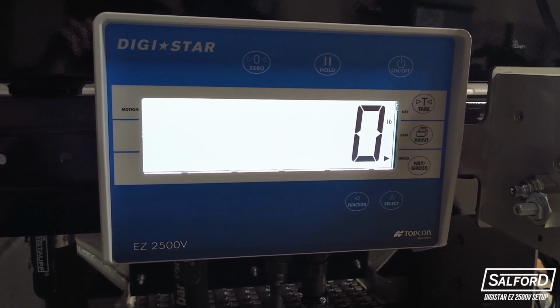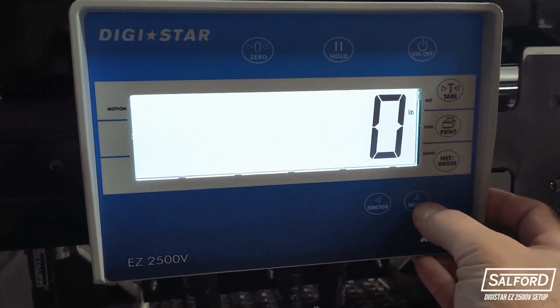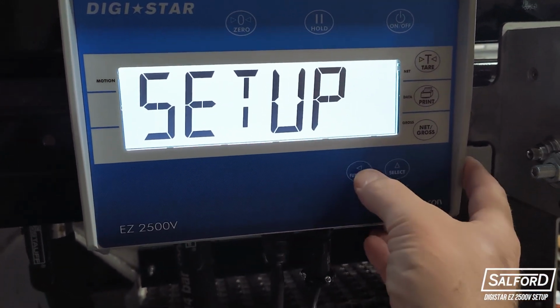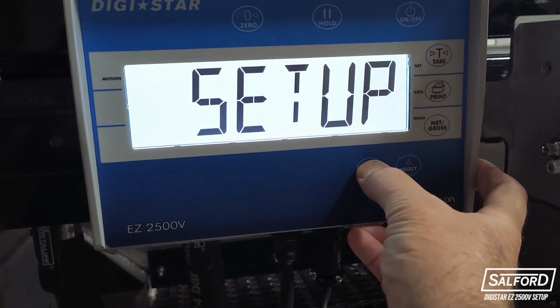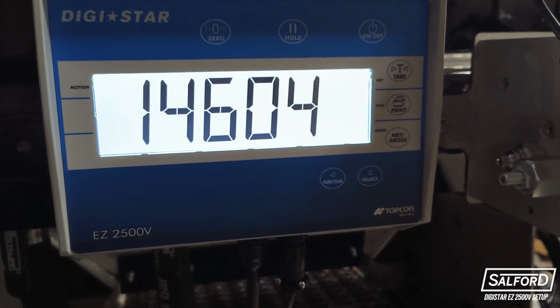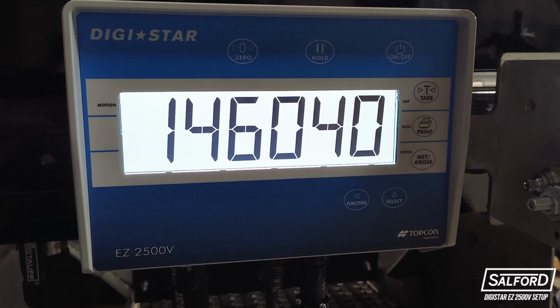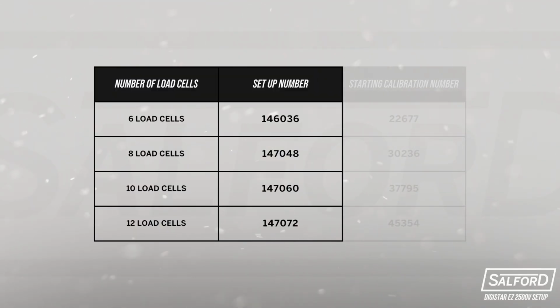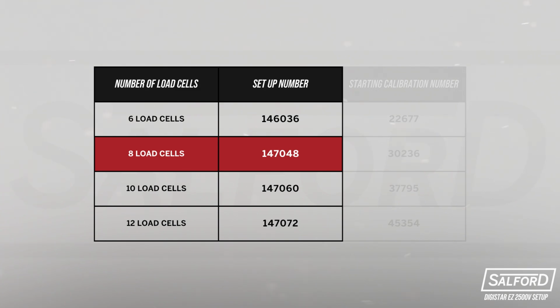To enter the setup menu, press the select button in the bottom right corner, which will display the word setup on the screen. Then press and hold the function button, which is beside the select button. Displayed on the screen will be the default setup number. This number will need to be adjusted depending on the number of load cells on your machine. Displayed on screen is the setup number that is associated with the given number of load cells. In this example, the machine has 8 load cells, and therefore, the setup number required is 147048.